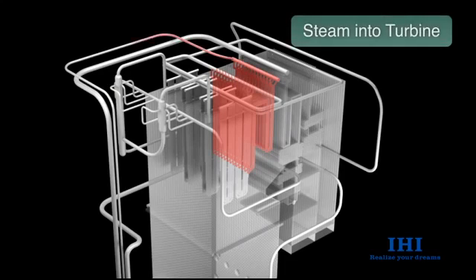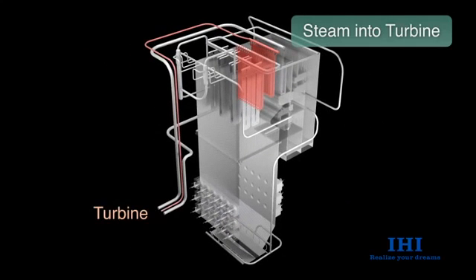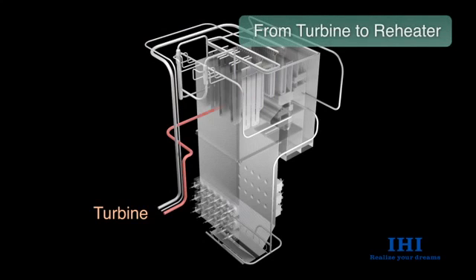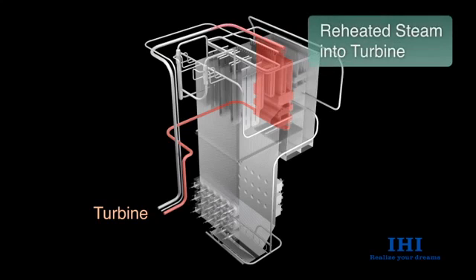The steam is sent to the high pressure steam turbine through the main steam pipe. The steam used in the high pressure steam turbine is returned to the reheater section of the boiler. The reheated steam is sent to the intermediate and low pressure steam turbines through the hot reheat pipe. The steam used by the intermediate and low pressure steam turbines is condensed by the condenser, and the cycle is complete. The water is reused as boiler feed water.